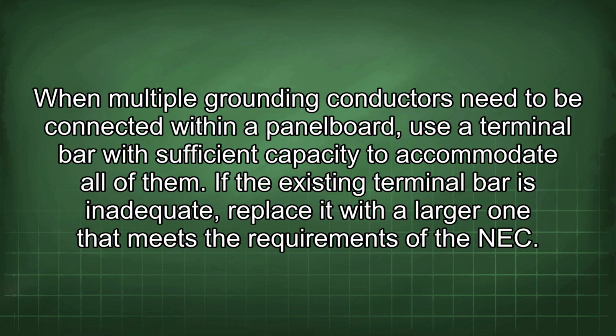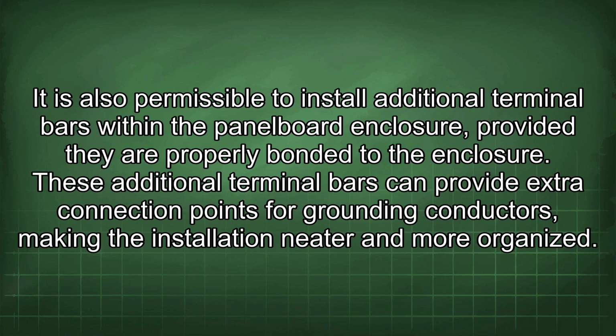When multiple grounding conductors need to be connected within a panel board, use a terminal bar with sufficient capacity to accommodate all of them. If the existing terminal bar is inadequate, replace it with a larger one that meets the requirements of the NEC. It is also permissible to install additional terminal bars within the panel board enclosure, provided they are properly bonded to the enclosure.